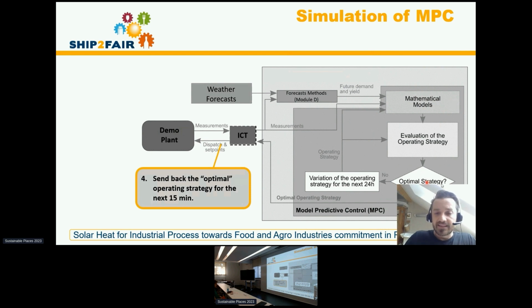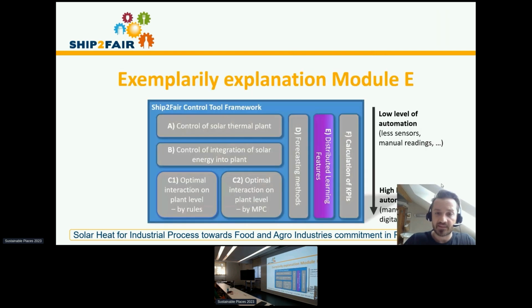This is then sent back to the real plant, and it's done every 15 minutes, closing the loop to make it a control. At the next 15 minutes, measurement data is received again, the mathematical model is initialized, the operating strategy is changed, and once the optimum is found, it sends back the optimal operating strategy for the lowest cost to the real system.